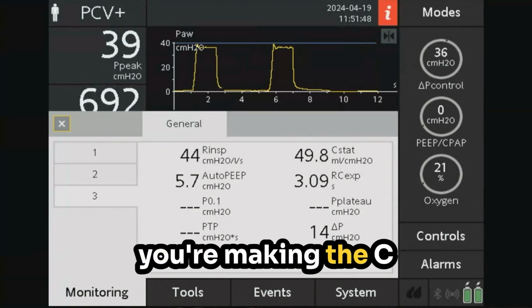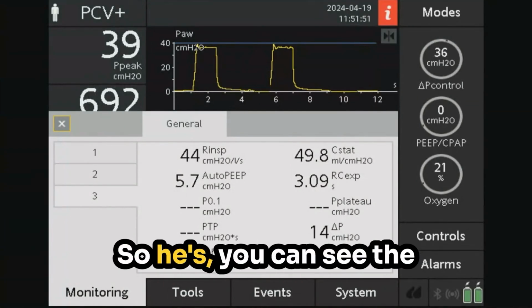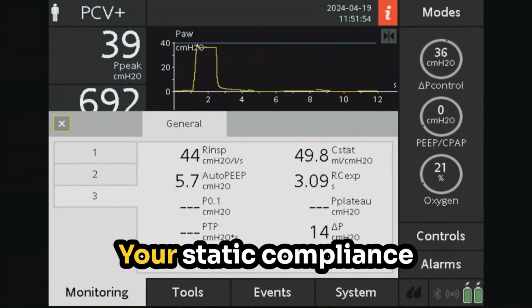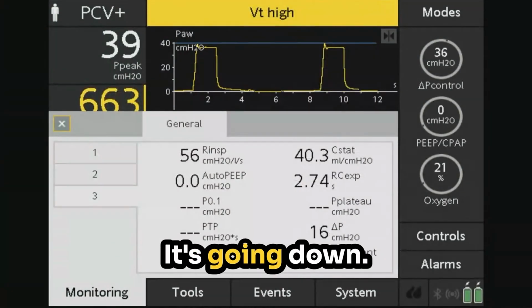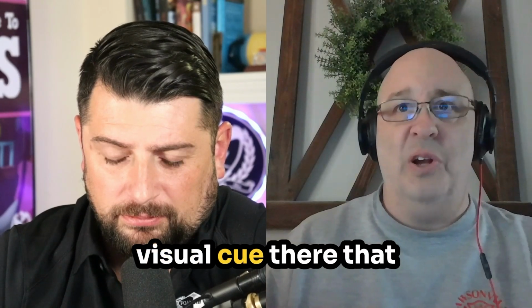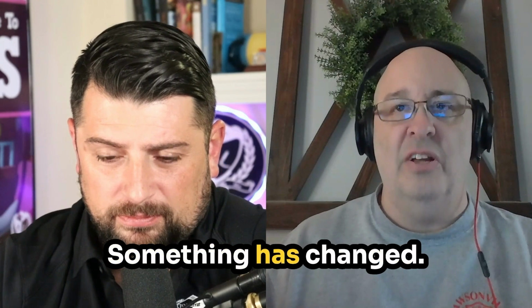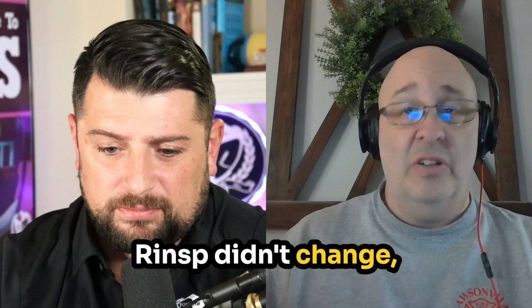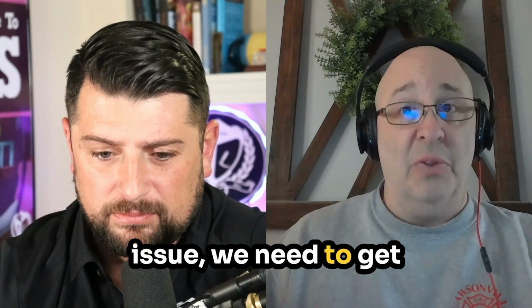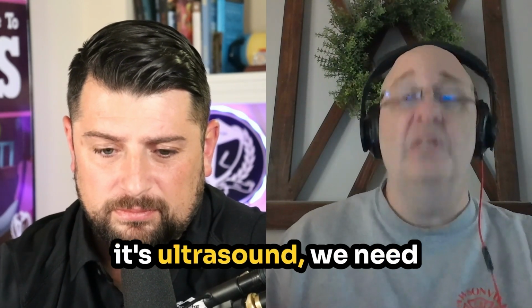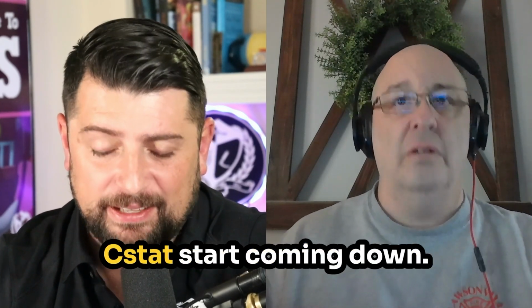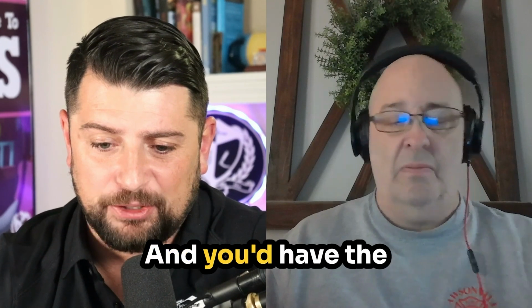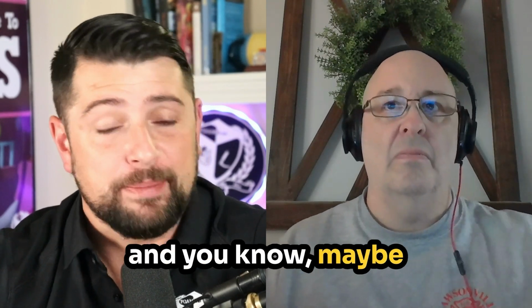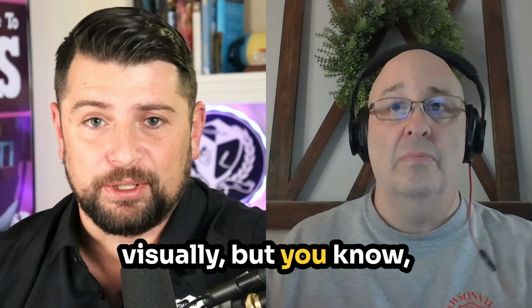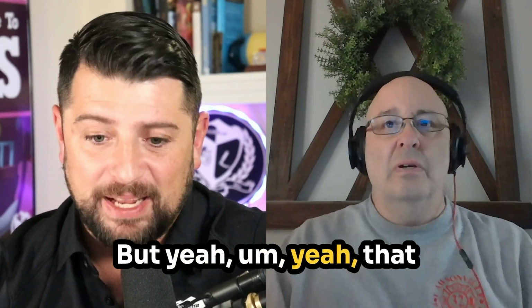So you're making the C stat drop. For people who are listening to this, you can see the C stat coming down. Your static compliance is taking a dump. It's going down. That's going to be a visual cue there that something has changed. Something has changed. Settings didn't change. Probably not an airway issue. We need to get on the chest. Whether it's listening, whether it's ultrasound, we need to get on the chest. Yeah, you'd probably see your oxygenation tank and C-stat start coming down. Correct. And you'd have the indication that, hey, something's up, and maybe you can see something on the chest visually, but I wouldn't bet on that. But yeah, that can be a tough scenario.